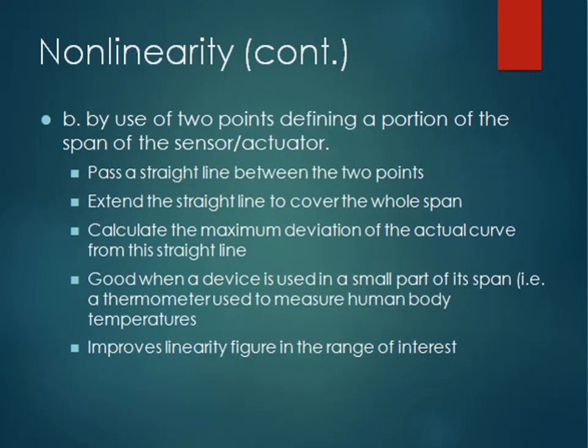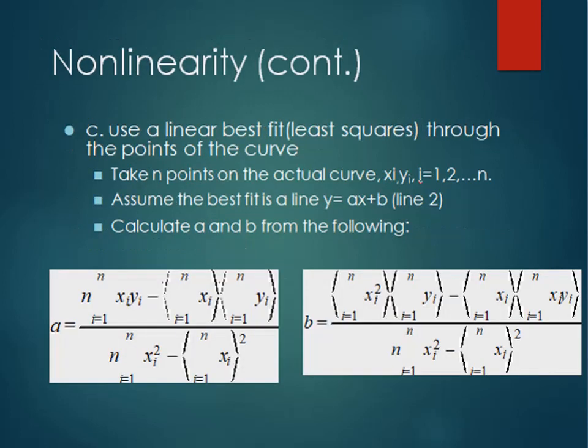Second method is by use of two points defining a portion of the span of the sensor or actuator. Again we pass a straight line between the two points, extend the straight line to cover the whole span, and calculate the maximum deviation of the actual curve from this straight line. It is good when a device is used in a small part of its span, for example a thermocouple used to measure human body temperatures, and it improves the linearity figure in the range of interest.